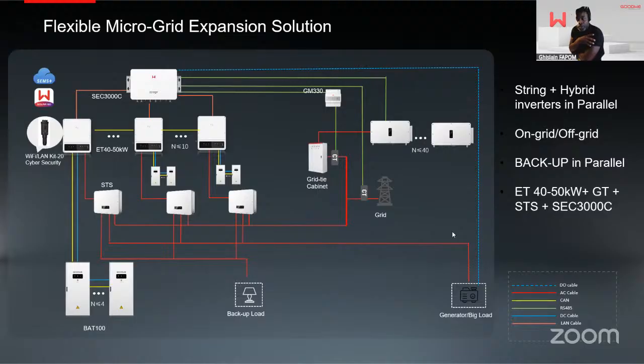And in these solutions, if we have a grid forming generator, I want to say our solutions are off-grid or microgrid solutions. They're not grid forming, meaning they cannot support a weak grid. They can work perfectly off-grid if the grid has fallen. But if someone adds a generator that has the ability to support a grid, then you can achieve a grid forming solution with our inverter and a third-party generator that can grid form. That was a key point because I had this question multiple times at Intersolar Germany.